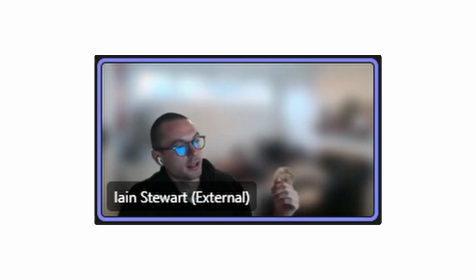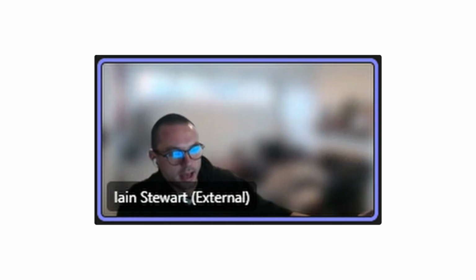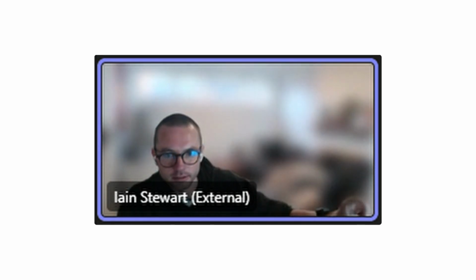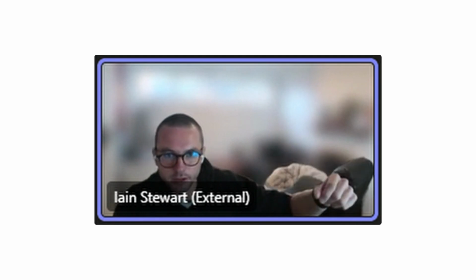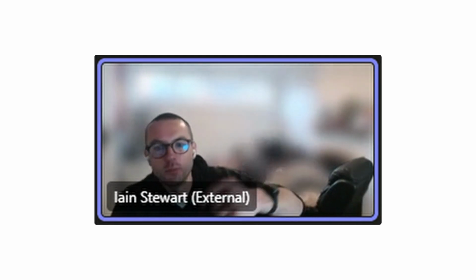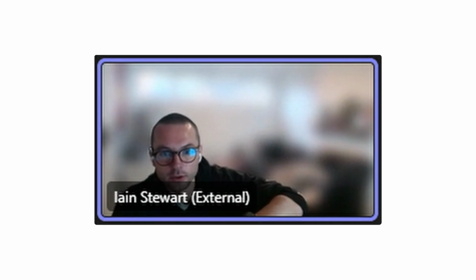And our chilled water leaving temperature set point of, say, 6 degrees Celsius. Really, what that's doing there is providing enough water. In this system as well, it's also looking at providing enough differential pressure, generating enough pressure to get the water to all of the air handling units in the system.